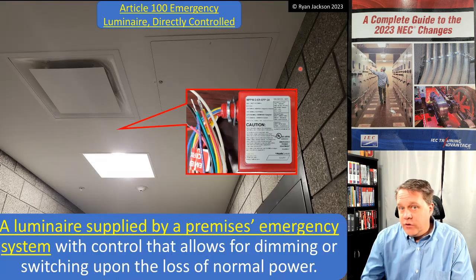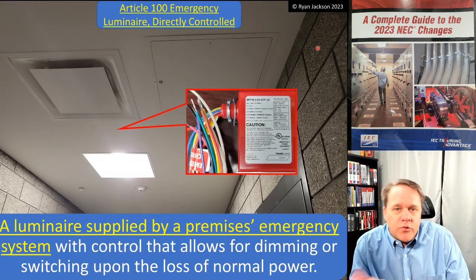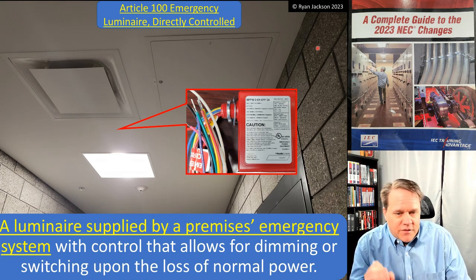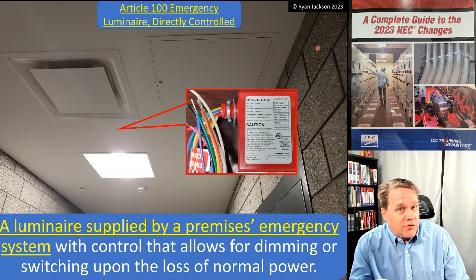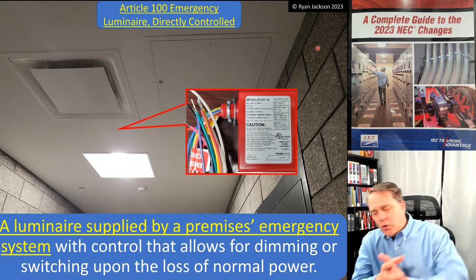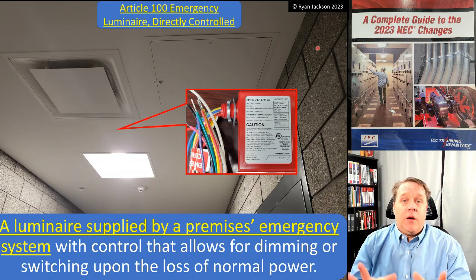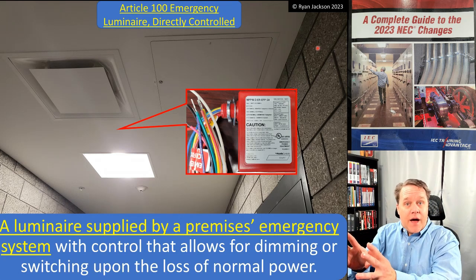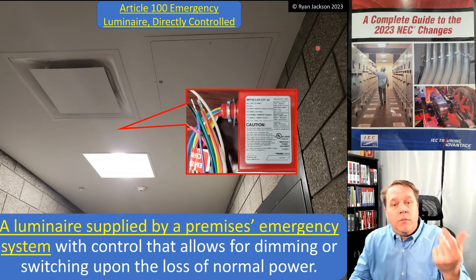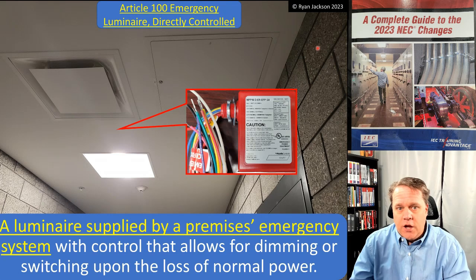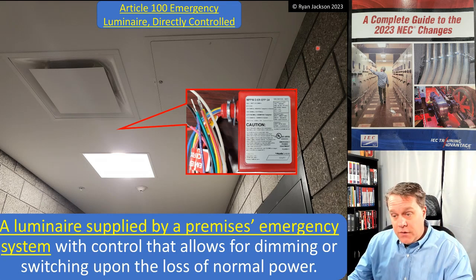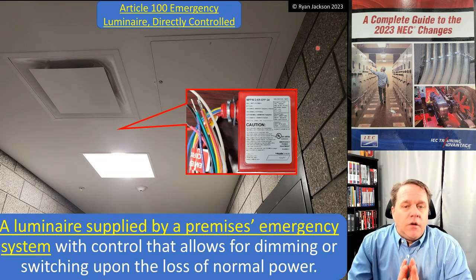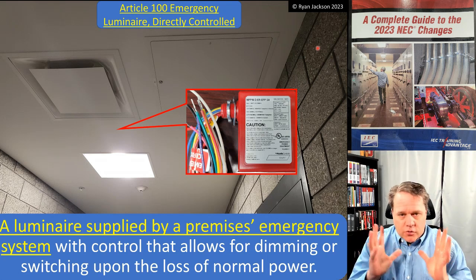The definition was revised for clarity. This would be a luminaire that's supplied by a premises emergency system with control that allows for dimming or switching upon the loss of normal power. If you don't have a backup power source, you don't have one of these. If all you have is a battery pack — like a bug eye, an exit sign, or an emergency ballast — this isn't what we're talking about. This is where we have an actual emergency system: a generator, fuel cells, whatever our backup system is.